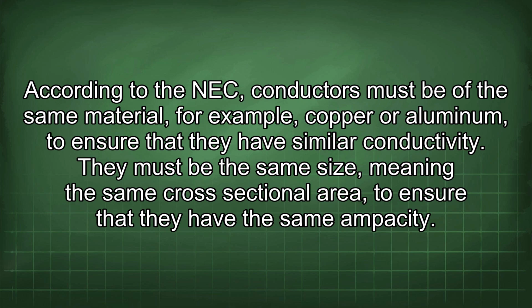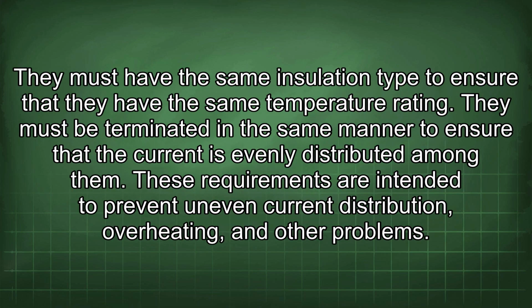According to the NEC, conductors must be of the same material, for example, copper or aluminum, to ensure that they have similar conductivity. They must be the same size, meaning the same cross-sectional area, to ensure that they have the same ampacity. They must have the same insulation type to ensure that they have the same temperature rating. They must be terminated in the same manner to ensure that the current is evenly distributed among them.